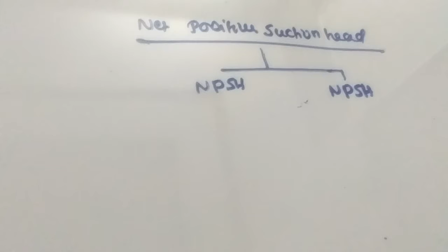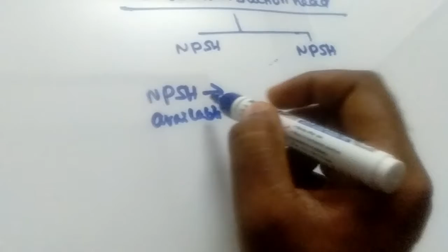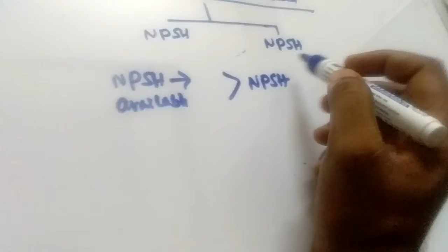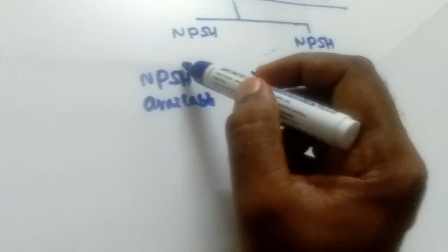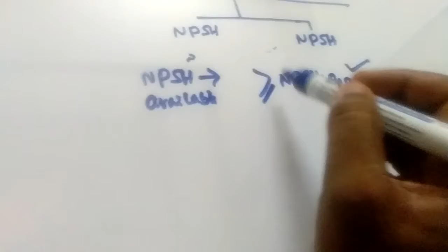Before purchasing any pump, we need to make sure whether NPSH available is sufficient, because NPSH available should be more than NPSH required. The required value depends on the manufacturer. Where we are installing the pumps, we determine the NPSH available. It should be more. If it is more, then the pump will work very easily and it is cavitation free.